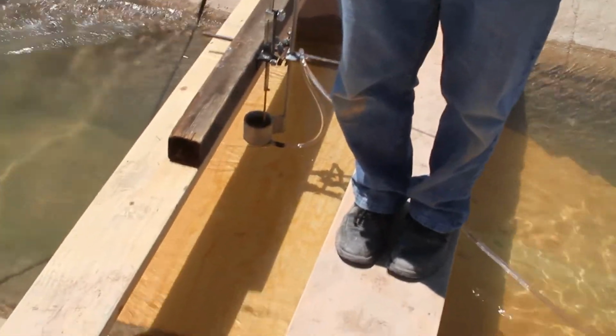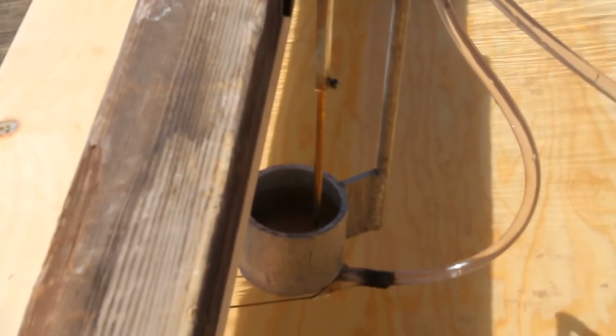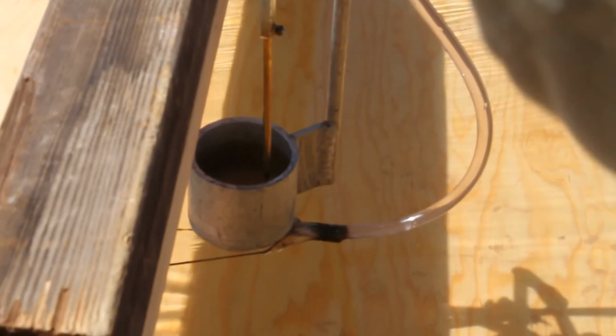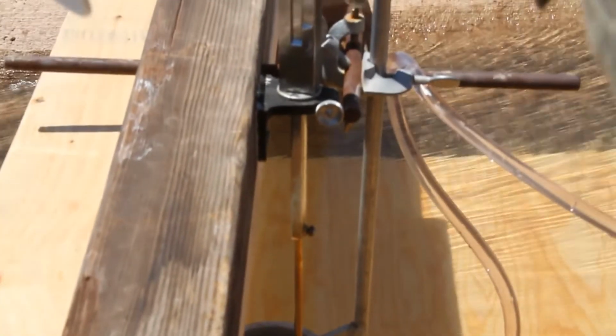All right. Can you show us what is running right now? What CFS is running? Let me see. When I subtract the 0 away, I'm ending up with a net of 0.733 feet of depth. And when I put that into the computer table over here, .733 gives me 10.12. Can you point to that one on the screen? 10.12. Thank you so much.